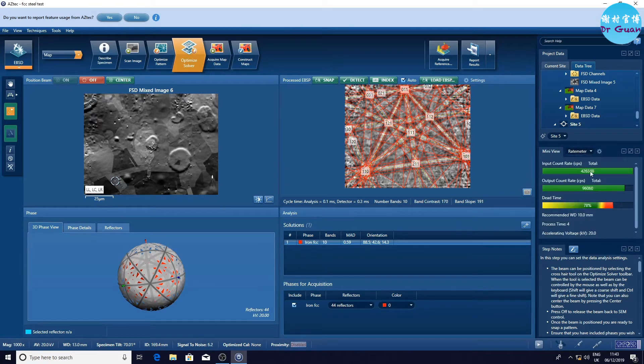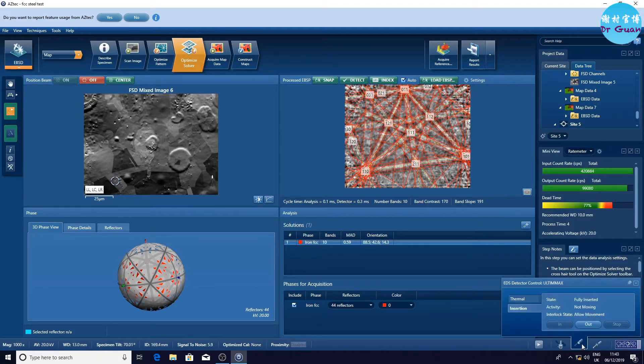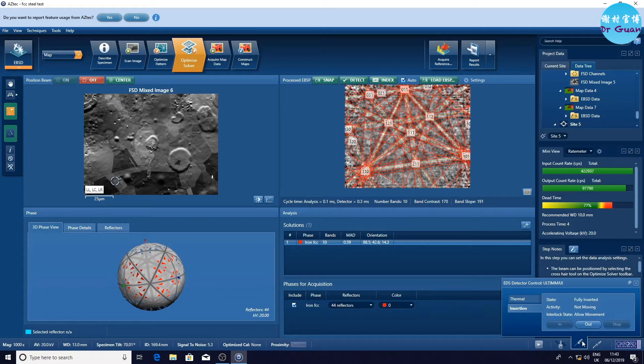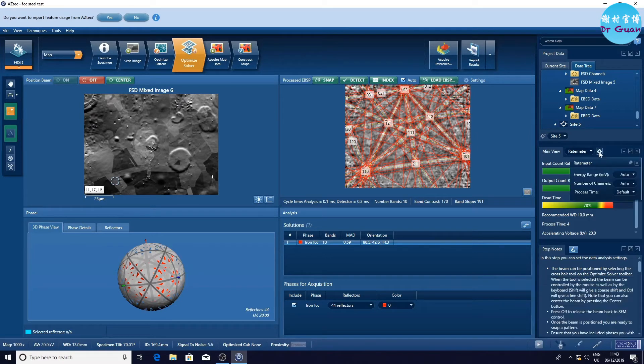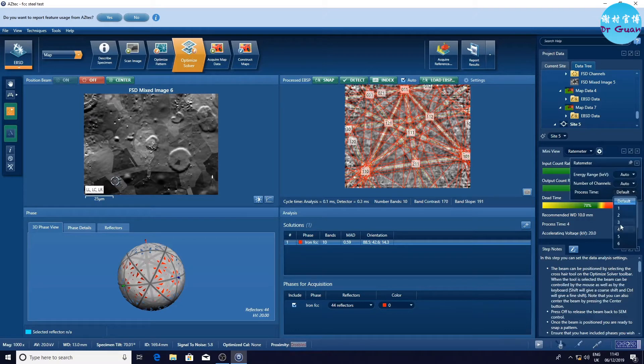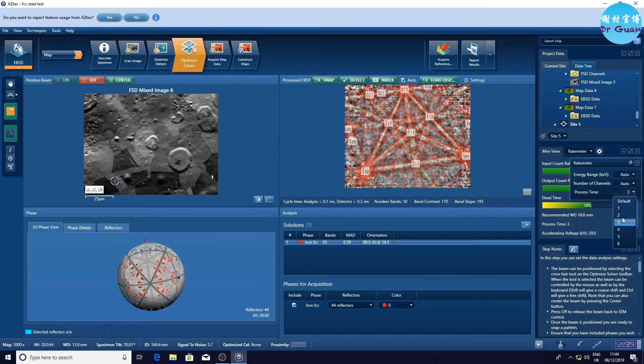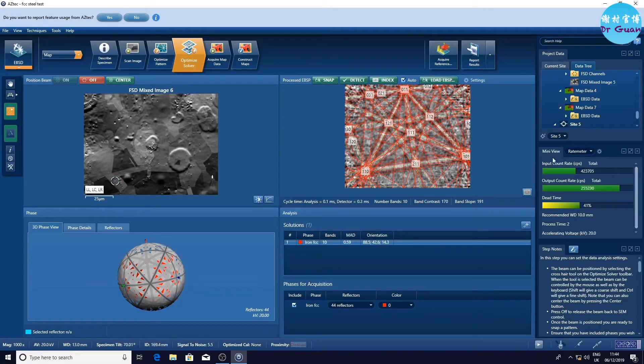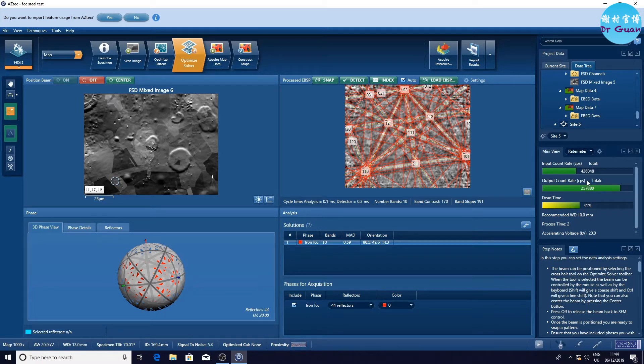We need to check the spectrum of EDS detector. Now you can see the dead time is 78%, which is very high. We need to decrease it down to less than 50%. We can choose to click the settings and decrease processing time to 3, which is still a bit high. So let's go back to 2, which is good. The other way to do this is we can retract the EDS detector a bit.